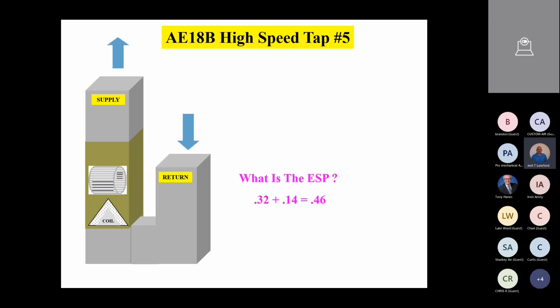So as we take a look at that chart, what is our CFM on that 1.5 ton AE air handler, high speed tap, 0.46 inches of static? What's our CFM off that chart? Anybody? 1,053.